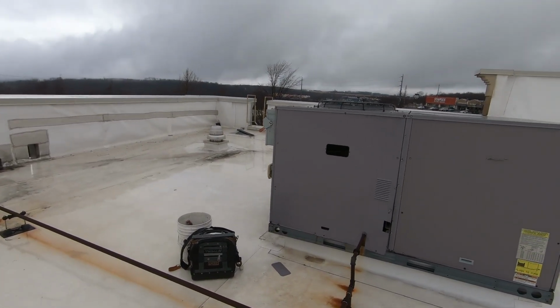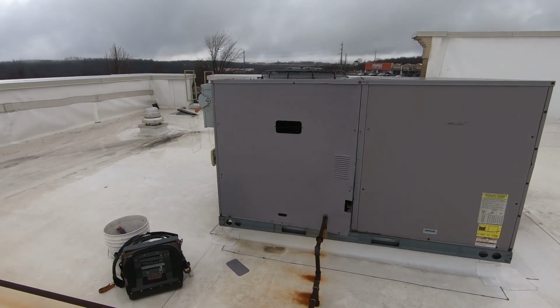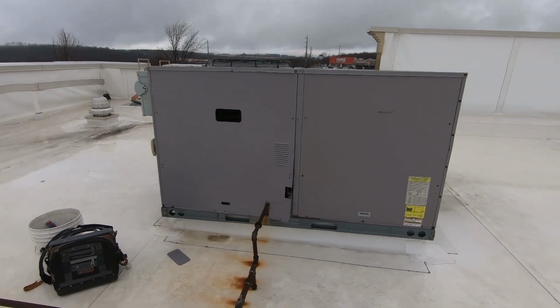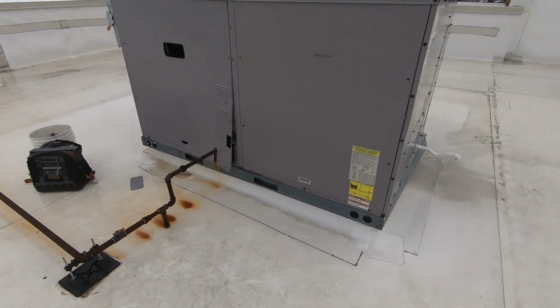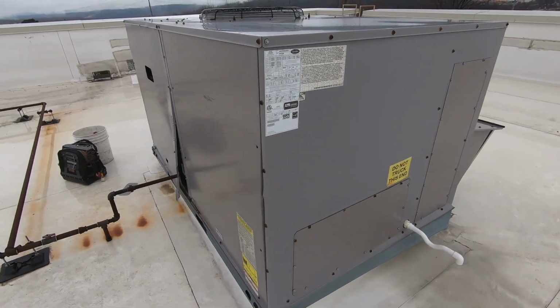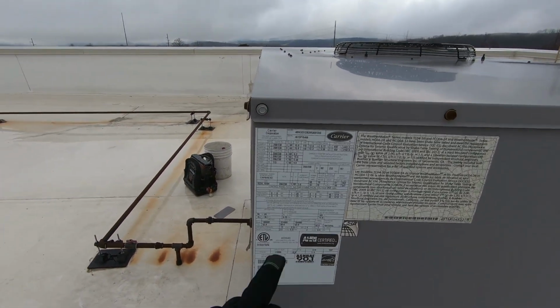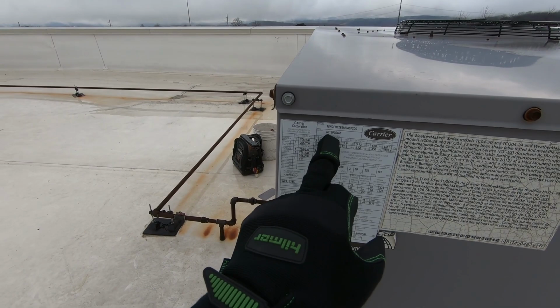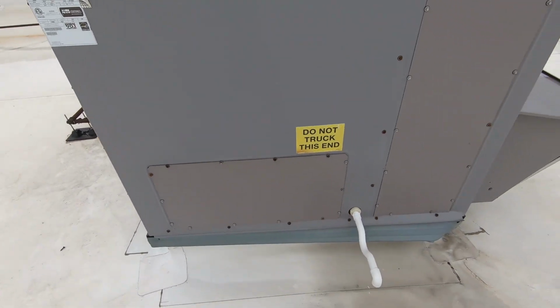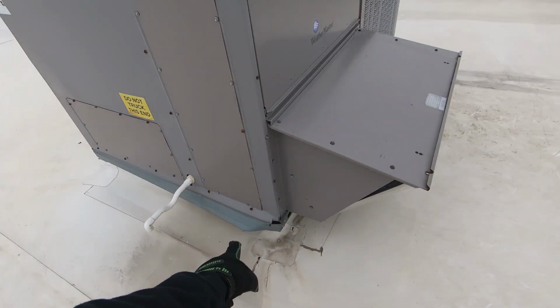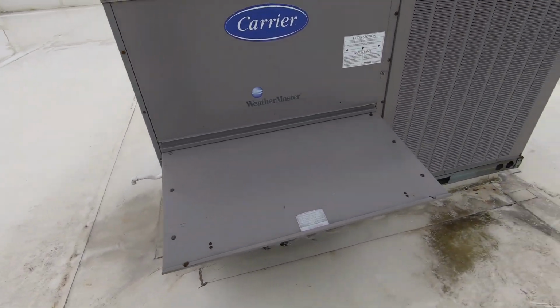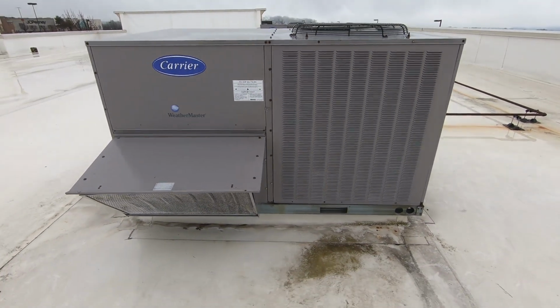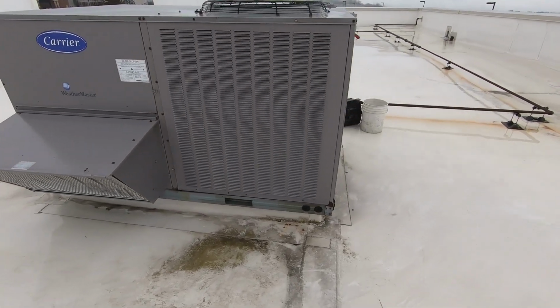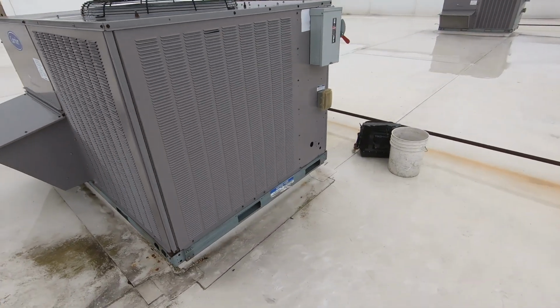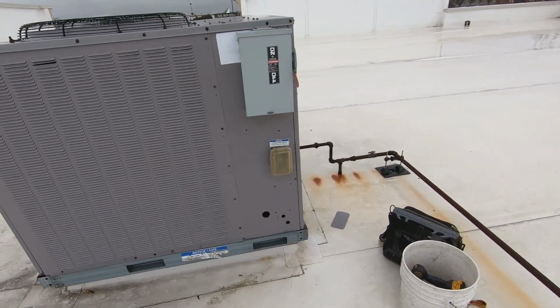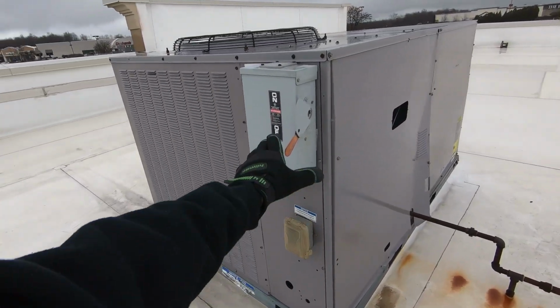Apparently the fire department's been here 3 times in one day. ADT also out here. Apparently this unit is filling up the store with smoke, so they shut it off. 2015 Carrier. We're gonna open it up. The curb looks like it's all dented and bent up. Take a peek at this thing and see what's going on. I'm guessing most likely bad blower motor, but we'll find out.